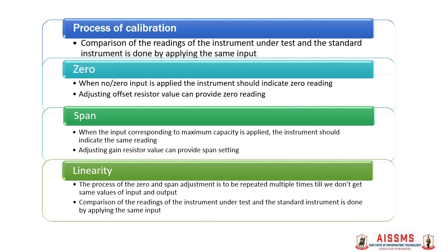Once this process is done, we need to go for the linearity setting. Here we apply various values of inputs to the instrument under test and the standard instrument simultaneously. We compare the readings given by the instrument under test with the readings given by the standard instrument. This process is repeated until both the standard and the instrument under test continue to give the same readings.